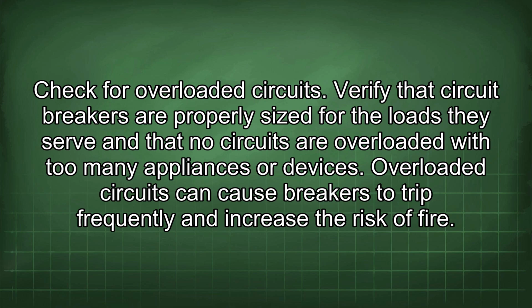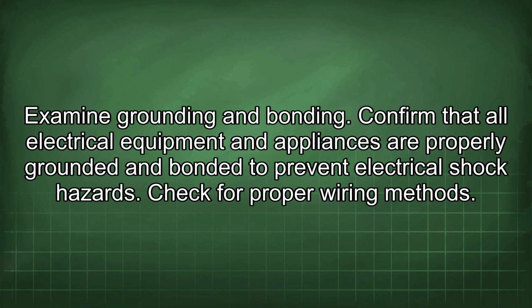Check for overloaded circuits. Verify that circuit breakers are properly sized for the loads they serve and that no circuits are overloaded with too many appliances or devices. Overloaded circuits can cause breakers to trip frequently and increase the risk of fire. Examine grounding and bonding. Confirm that all electrical equipment and appliances are properly grounded and bonded to prevent electrical shock hazards.